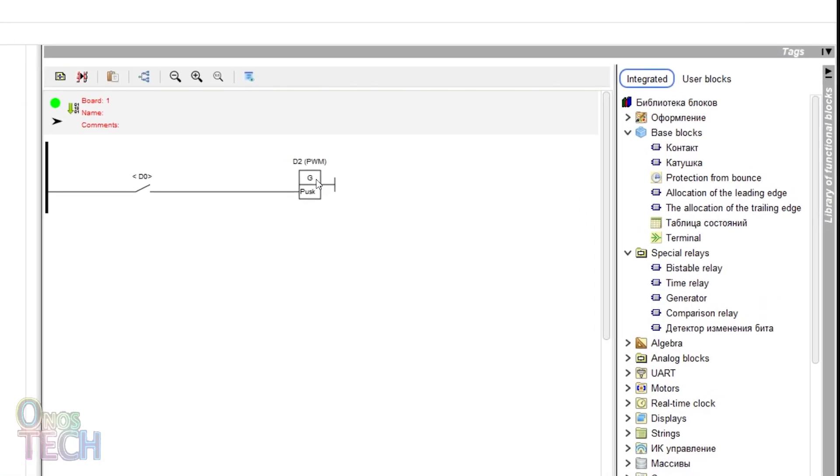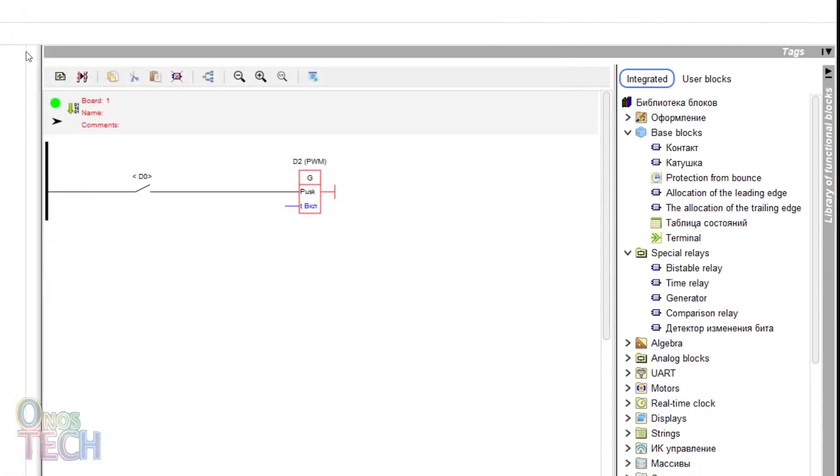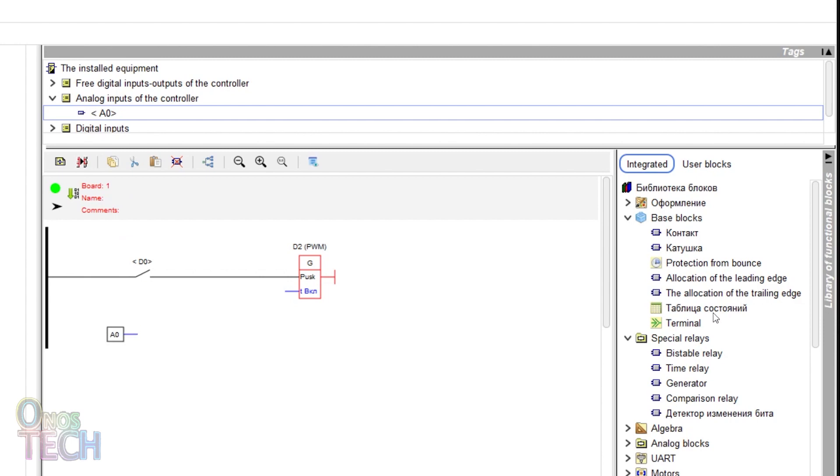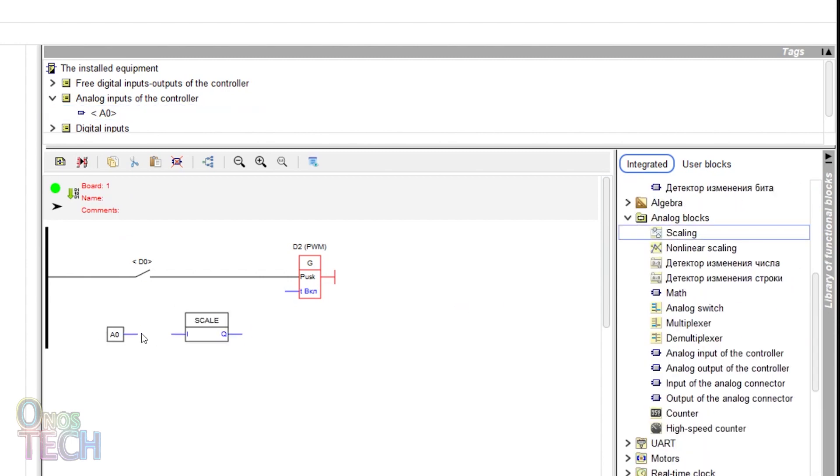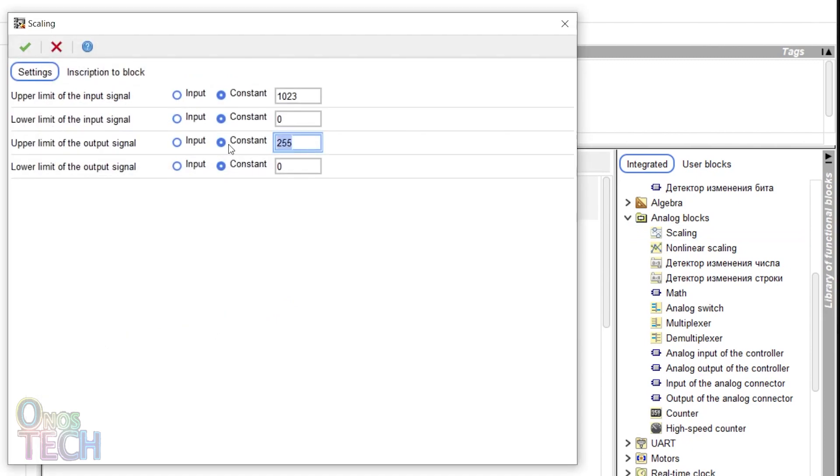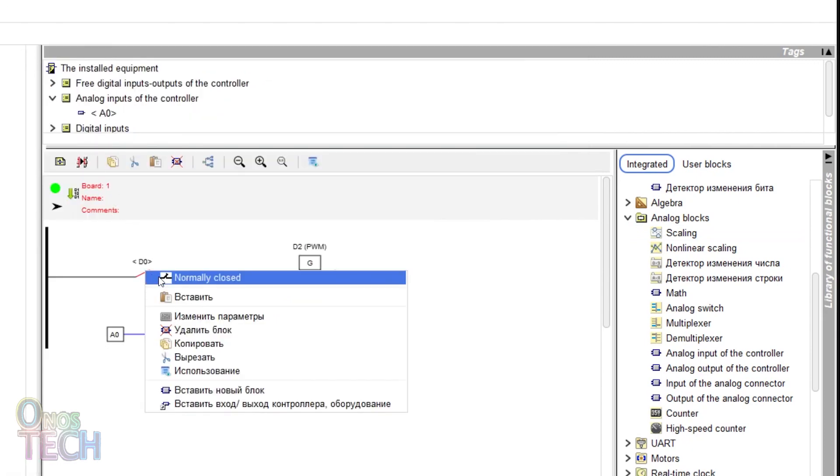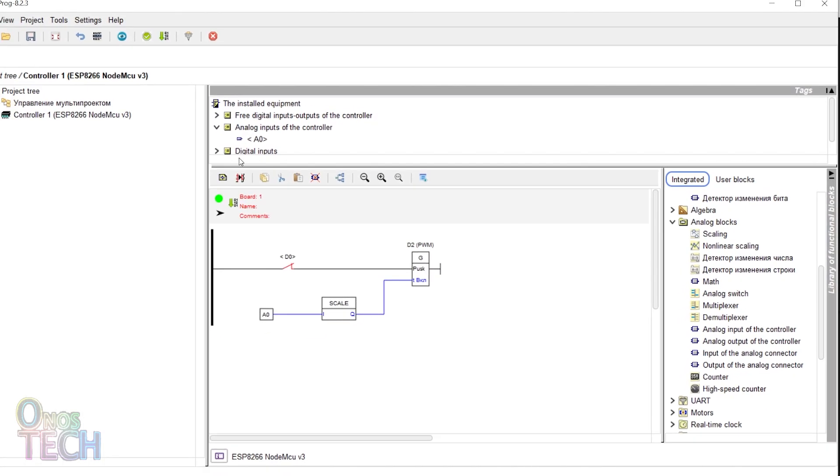For the symmetrical multivibrator, select the input type On Upduration. Insert the A0 analog input and a scaling block with the upper limit of the output signal set to 255. Right-click on the D0 contact and change it to Normally Close.